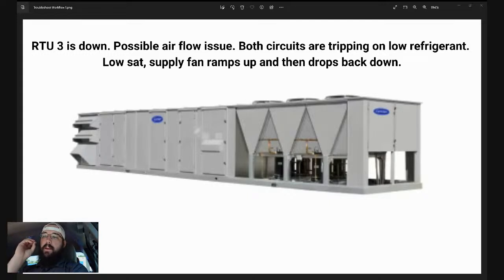If you don't know what the logic is trying to do, that is where the manual comes into play. The sequence of operations built into the manual, while it may not be 100% complete, will typically give you a really good idea of what that unit is trying to control. Now, some of those sequences of operations can be lengthy. They've got pages written, an entire section of the manual, that describes every little step in that process of what it's trying to do: start up, shut down, static, this, that.